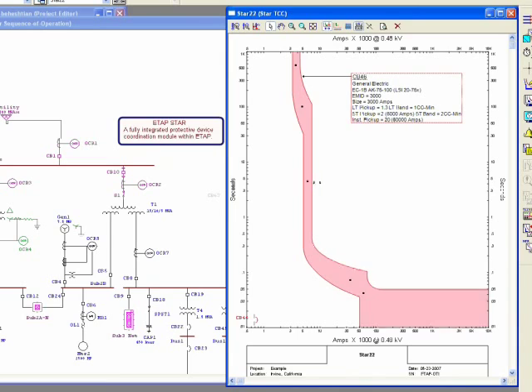Short time pickup—in this case, I don't have a short time, it's instantaneous because it says LI. If I select with LSI, I have to check this checkbox so it shows my short time band accordingly. In fact, EM is one of the old trip devices.